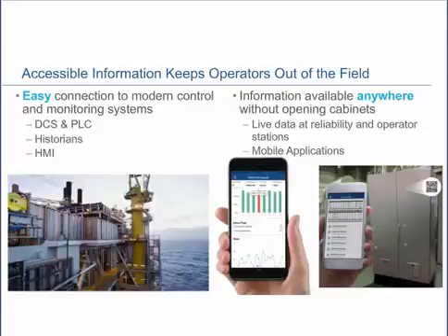And also we talked about integration of data. So you're able to pull that information from within the system to any of your external components or external systems, PI, HMIs, any other historian. The key thing is it is using OPC UA, which again is, I think, the first generation that's had OPC UA servers embedded in the protection system. So that now whenever you're trying to get to that data, you're able to browse.